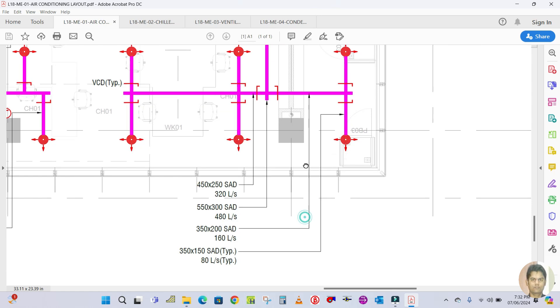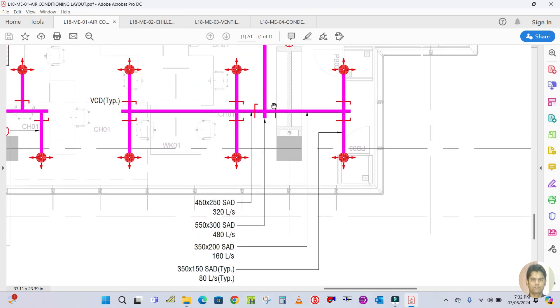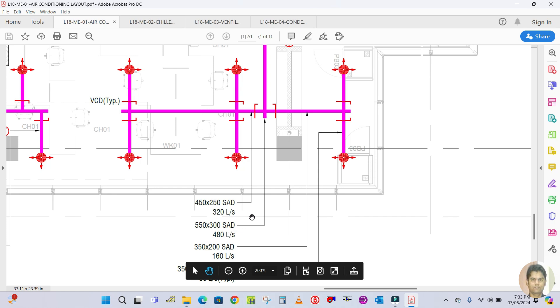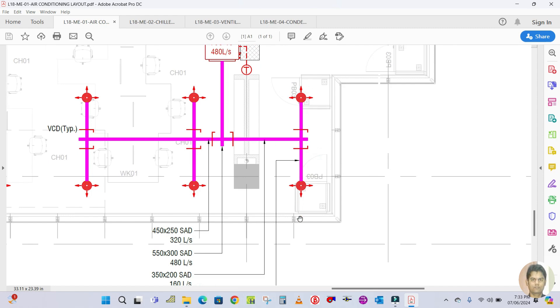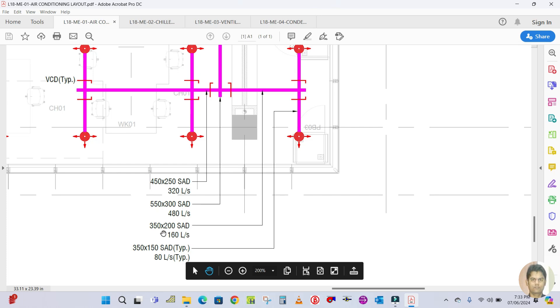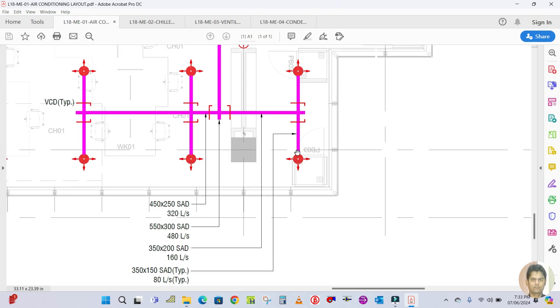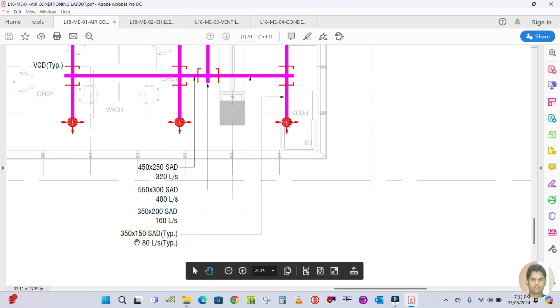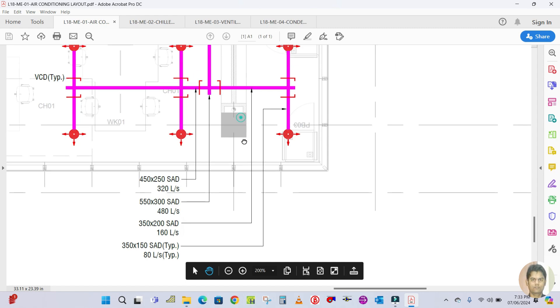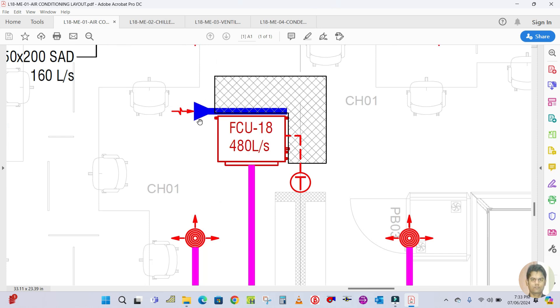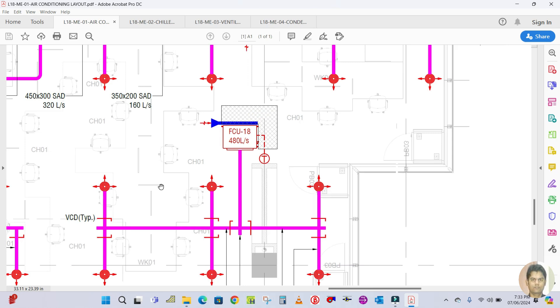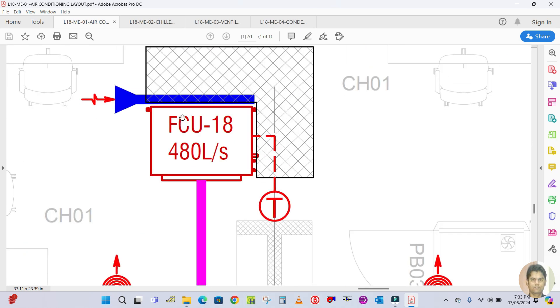The right side is the main duct, which is 550 by 300 with 480 liters per second. The right side branch duct is connected with two diffusers, and the duct size is 350 by 200 with 160 liters per second. From there, two branches at 350 by 150 carry 80 liters per second each. The blue color duct is the return air duct, which takes air from the room and returns it to the fan coil unit.